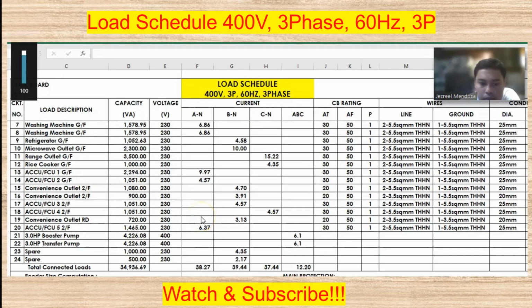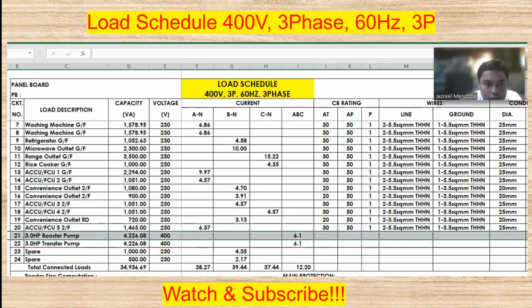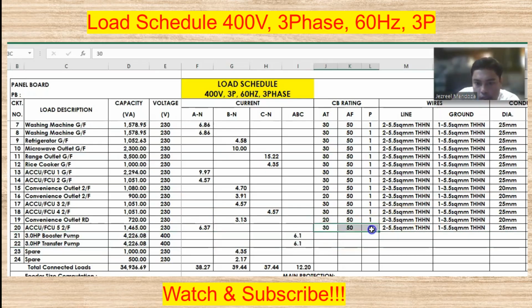And then for the 3-phase booster pump, circuit number 21, 22, we can use this 30 ampere circuit breaker, 50 ampere frame, and then this pole must be 3. Sir, bakit 3? Because it is 3 phase.